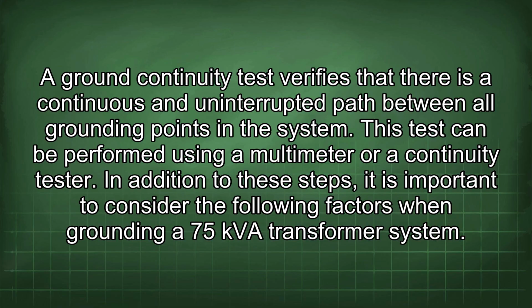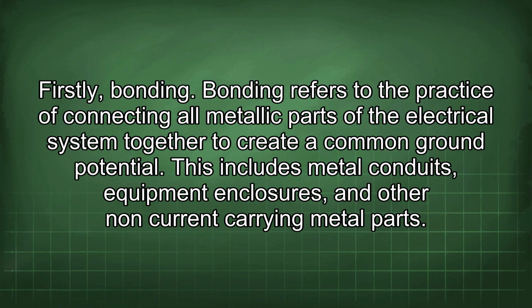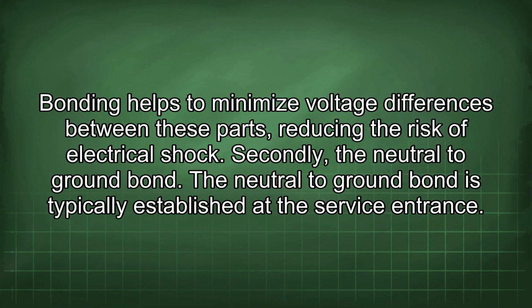In addition to these steps, it is important to consider the following factors when grounding a 75 kVA transformer system. Firstly, bonding. Bonding refers to the practice of connecting all metallic parts of the electrical system together to create the common ground potential. This includes metal conduits, equipment enclosures, and other non-current carrying metal parts. Bonding helps to minimize voltage differences between these parts, reducing the risk of electrical shock.